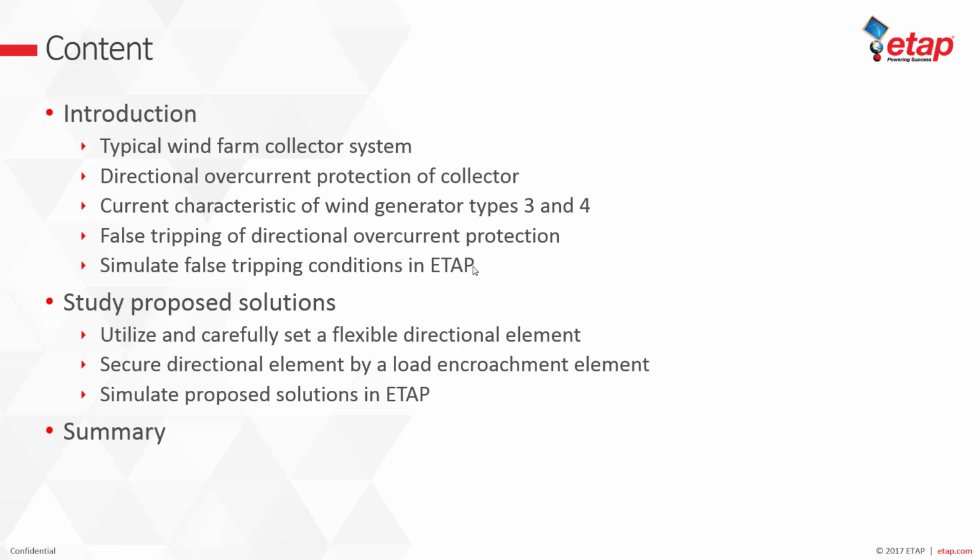And then we look at the proposed solutions, which are utilizing and carefully setting a flexible directional element, or securing the directional element by a load encroachment element. We simulate both solutions in ETAP and we look at the pros and cons of these two approaches. And finally, we'll summarize this presentation.